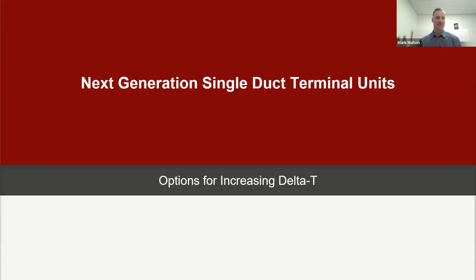And I'm seeing a hand raise from Tom. Tom, do you want to weigh in? I think the lowest you can put in is 0.3 GPM. 0.3 GPM is the smallest size manual or automatic balancing valve that we see manufacturers make. So even if we put in 0.2 or 0.1, if we approve submittals, if it goes all the way through, the build team starts building, it's a 0.3 GPM box. We cannot balance the box lower than 0.3 GPM. So that's the absolute minimum.